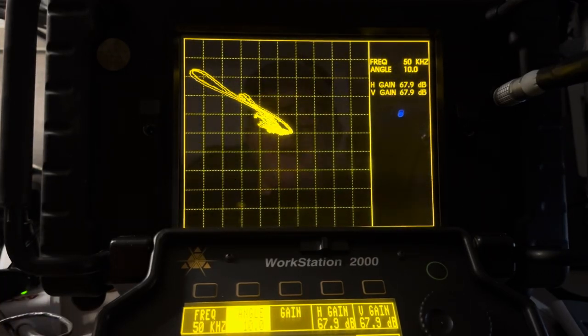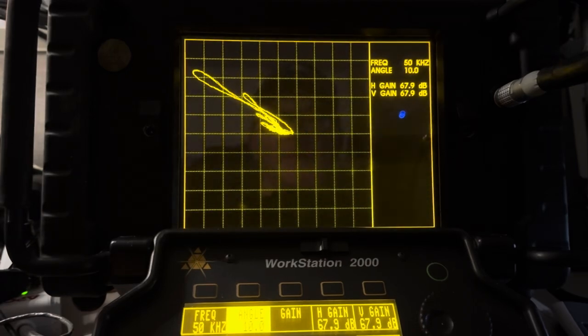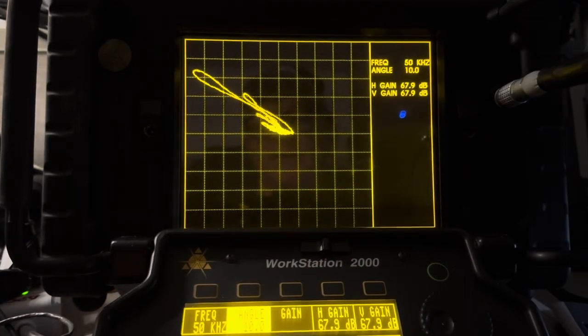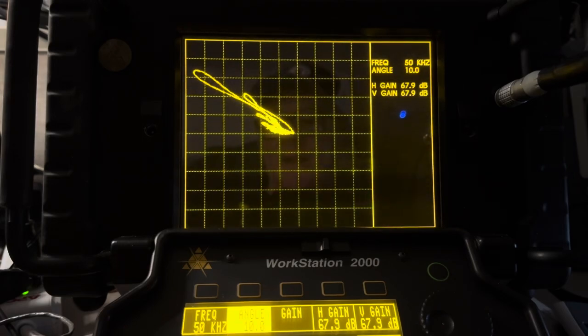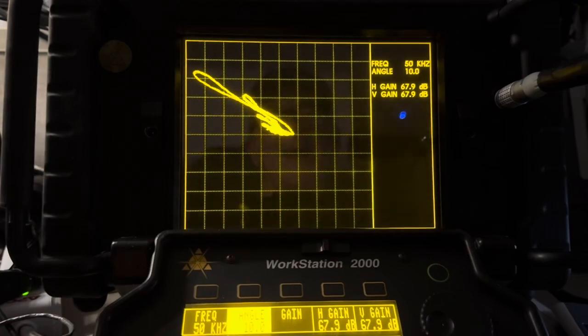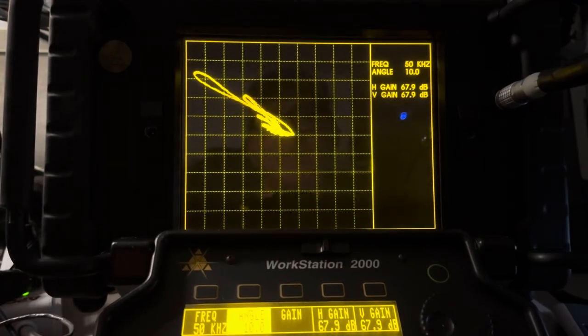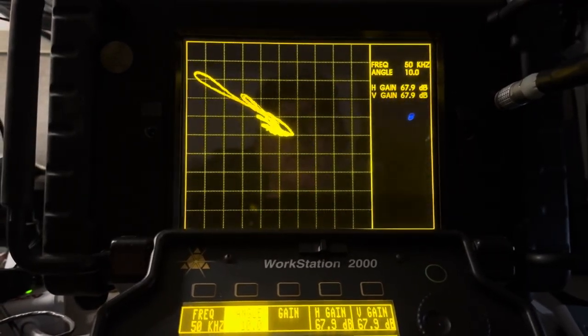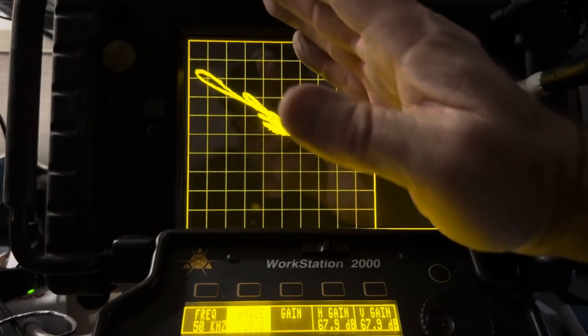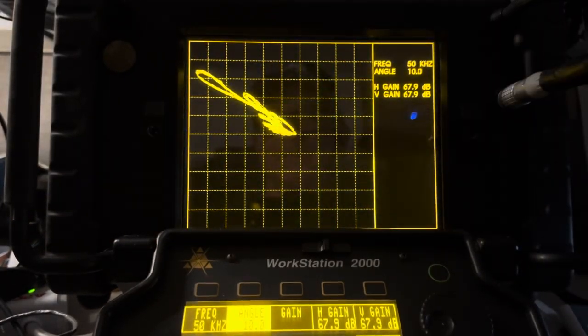If we had any ID flaws in the tube, it would take a long time for the eddy currents to penetrate from the inside surface through the encircling coil to the ID. But since we don't have any, all we have is flat bottom holes from the OD, and those are all very close to the coil. That's why everything is laying over there with not a lot of phase lag.